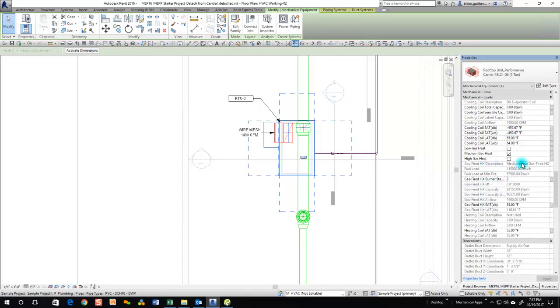Gas-fired heat exchanger. Because we have a performance table, we were able to include the 3 heat settings offered from Carrier's line. In this case, these are all the values that we're calculating or pulling from the performance table. The efficiency rate here is being used to calculate capacity, and this capacity value and airflow are being used to calculate the discharge air temperature.